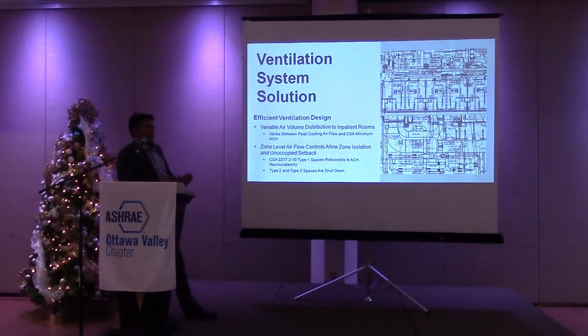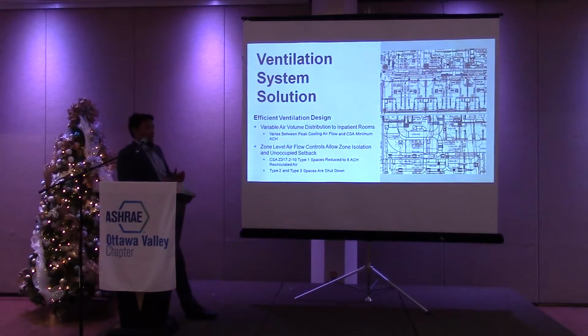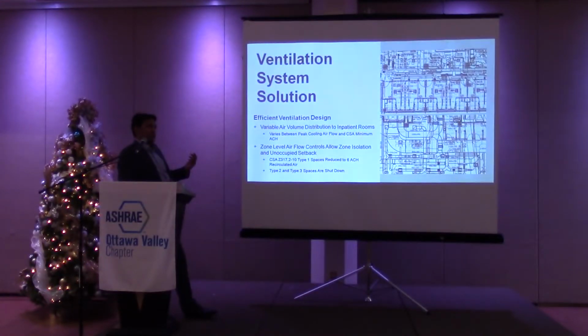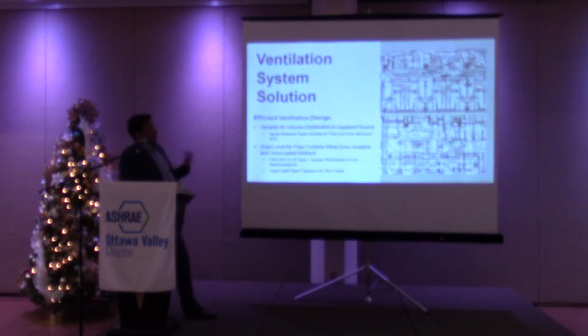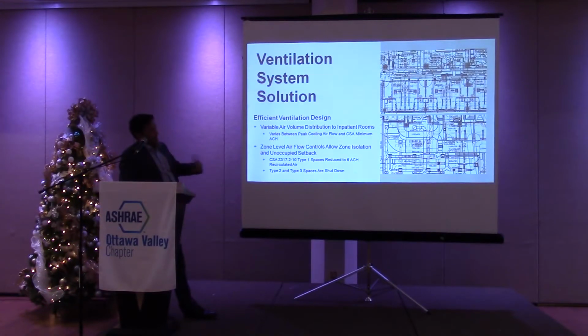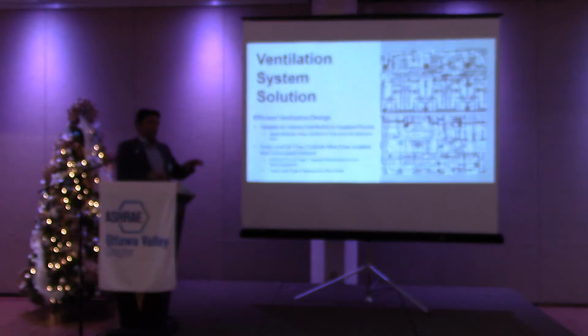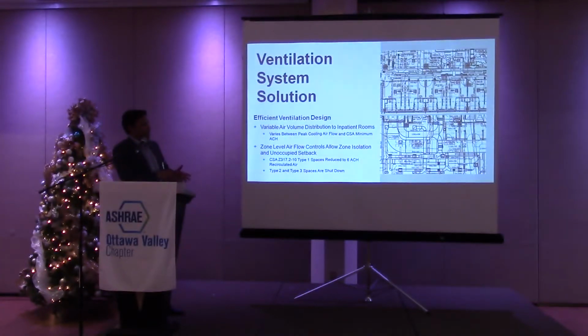What that allowed us to do is, in those areas, the facilities can schedule those areas to go into unoccupied mode. We have occupancy sensors in that space, and that can also drive the air changes up and down in those spaces as required. So this is as simple as scheduling your light switches in your space. We have large air handlers that serve a number of different areas, but all these sub-departments can vary down, either shut off completely, depending on the space type, or we go to the minimum air changes.